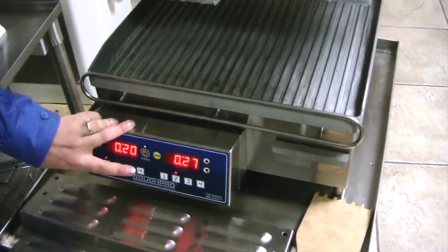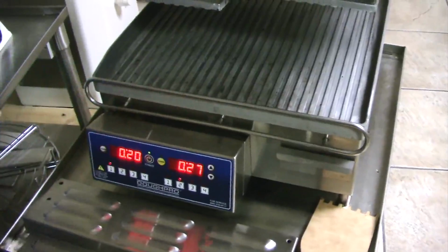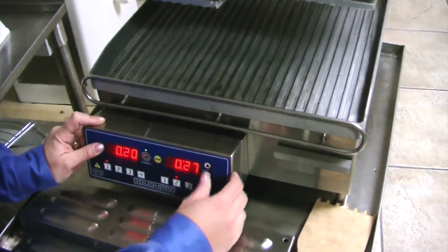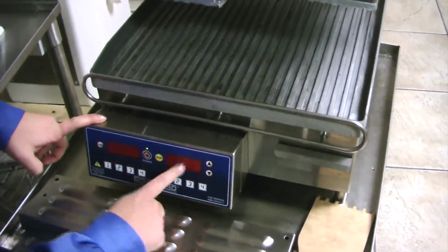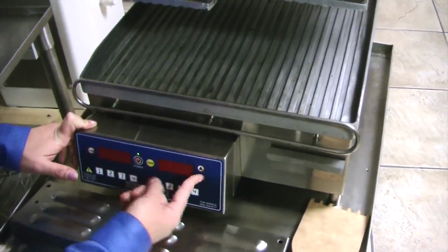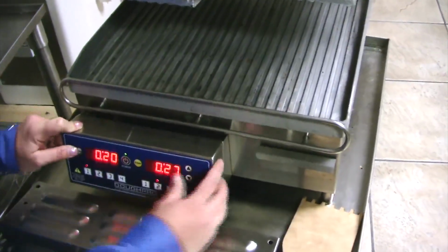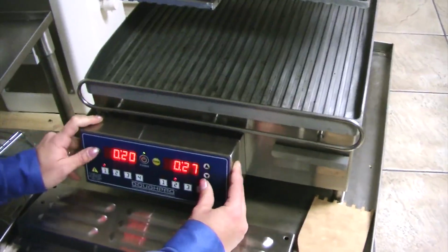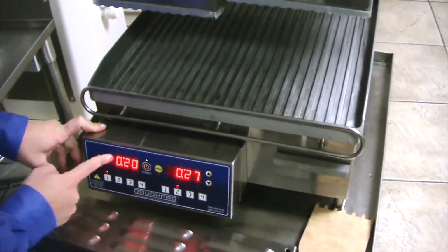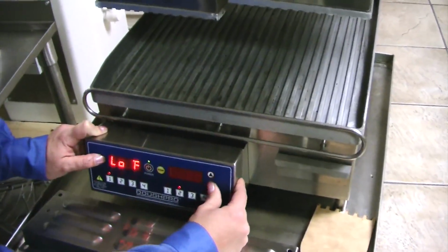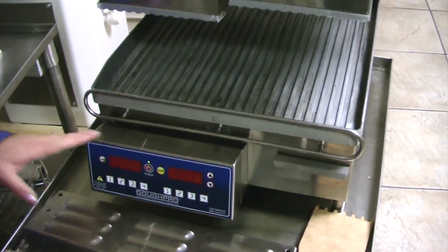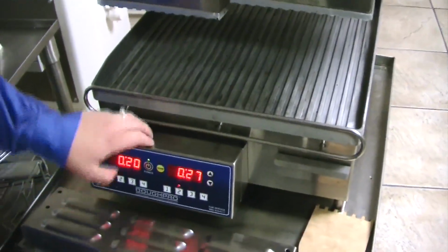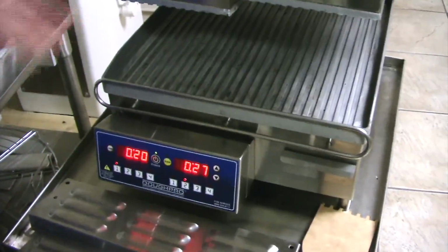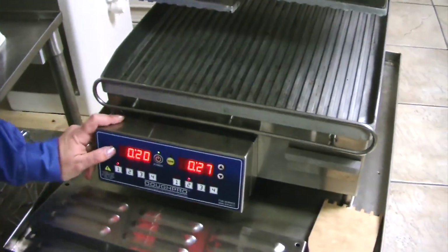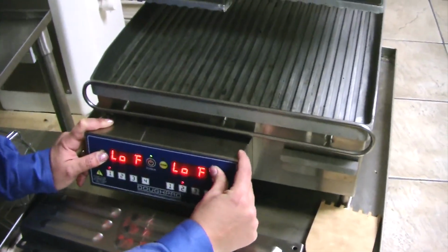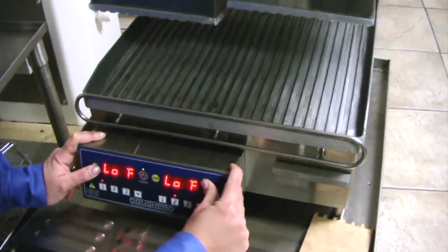Now, if your controller says PROB, it'll flash on one side. If you hit the temp button and the up arrow, one side will tell you PROB. If you hit the temp button and the down arrow, the left side, well, if that says PROB, then it's nice that the control tells you which zone you might need to change your sensor. If it's giving you a probe on the right side, that's telling you that you're upper right.